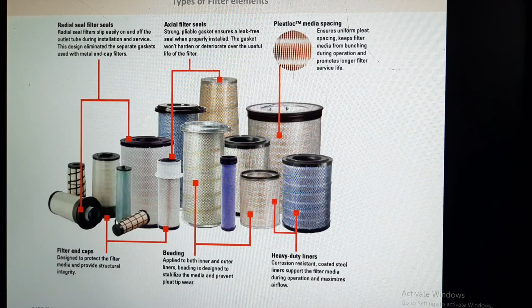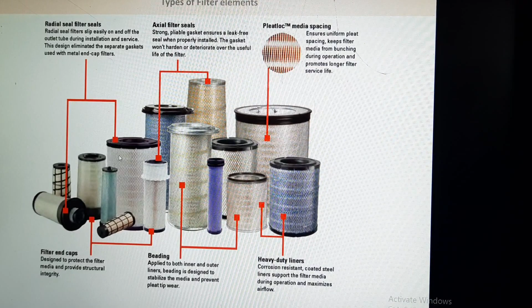Sometimes the radial seal filter elements also provide structural rigidity to the filter element, as well as holding the whole element so that it is equispaced. If you talk about the mesh size, the micro elements, the fiber mesh, the equispaced pleats are created in the filter element. So when you clean the air filter element, it is very important that you don't hit the air filter element, so that the equispaced filter mesh is not damaged.